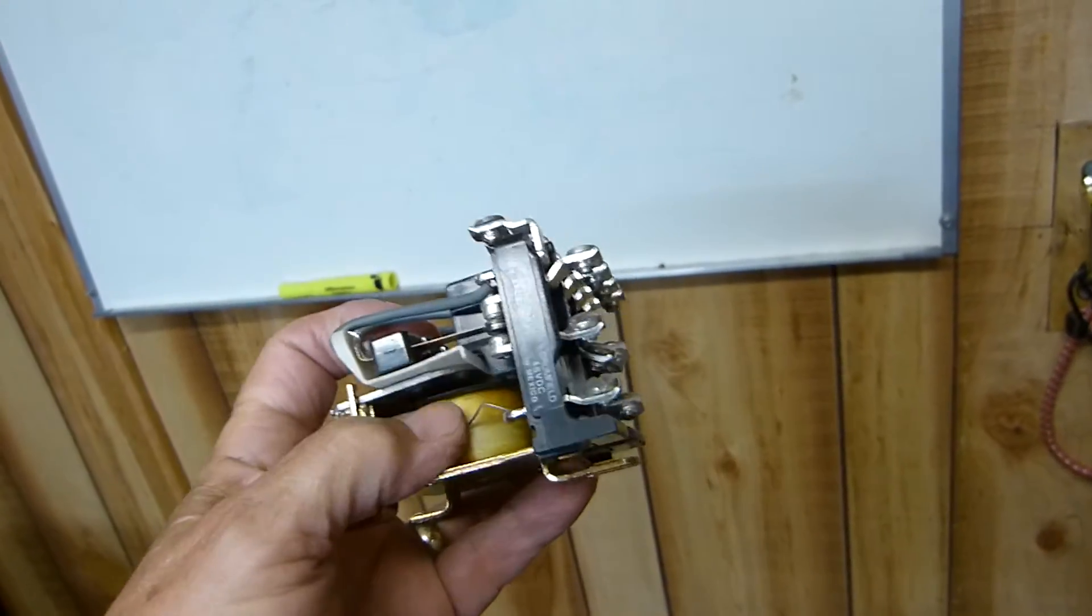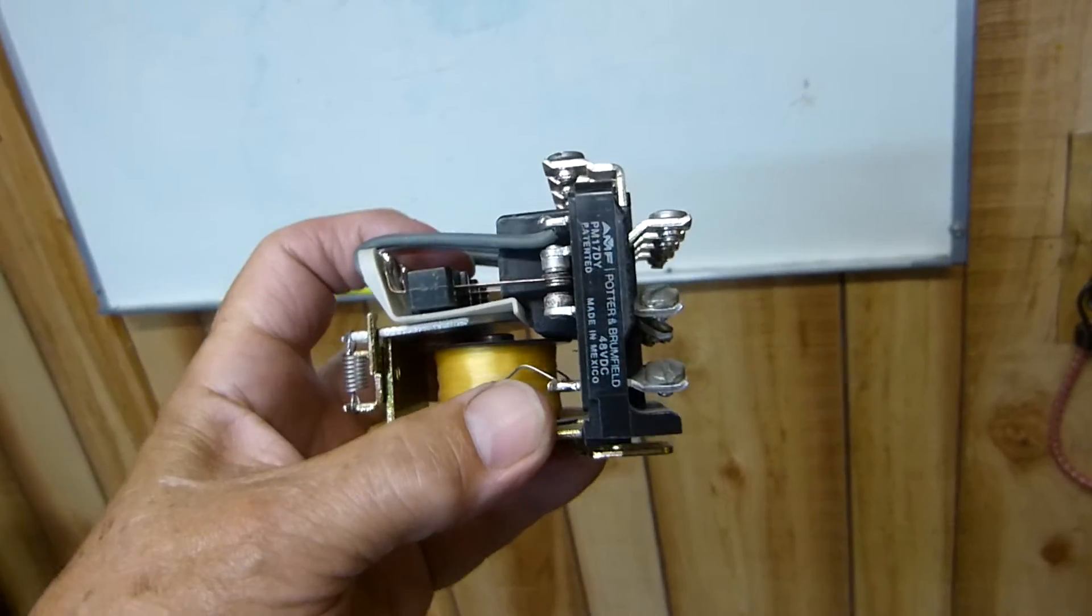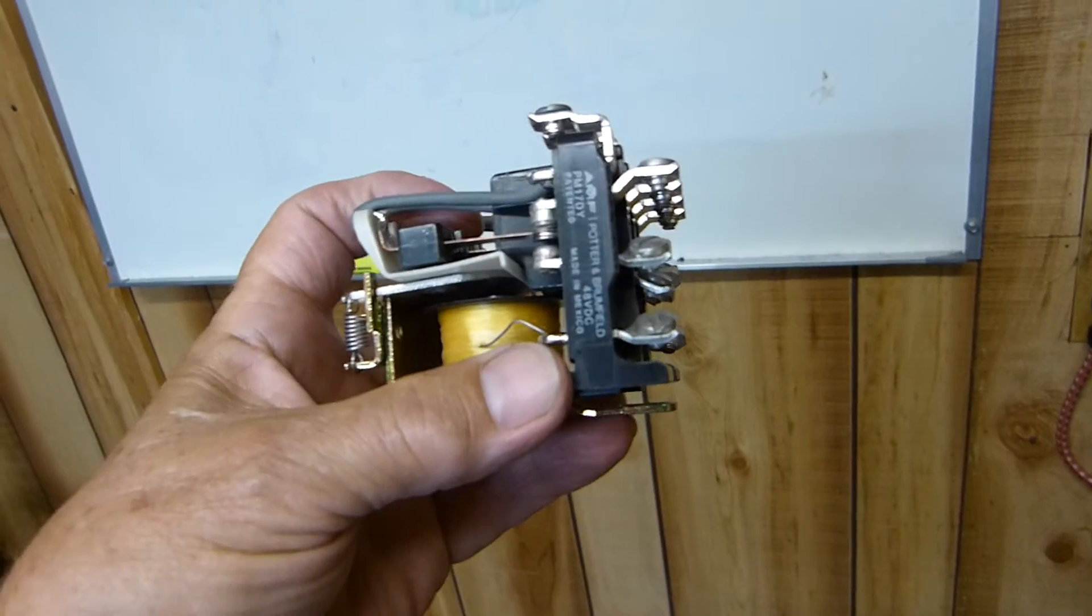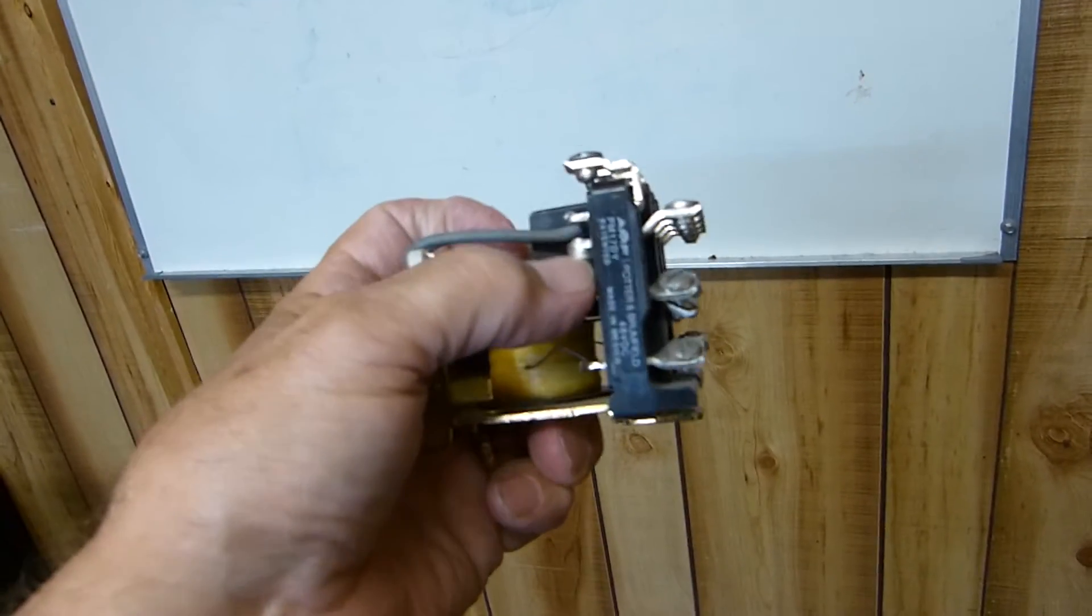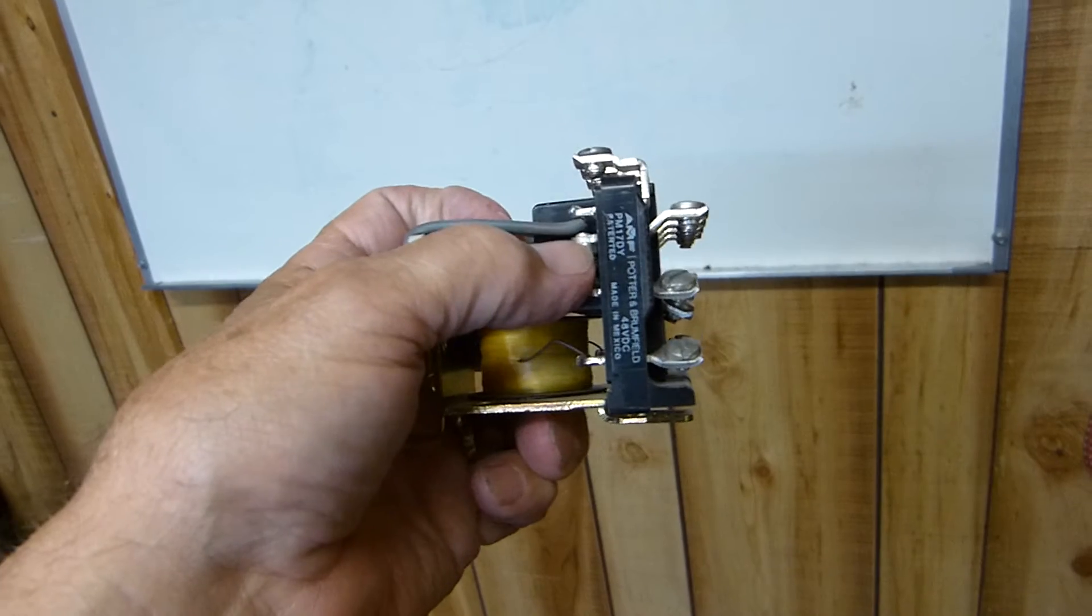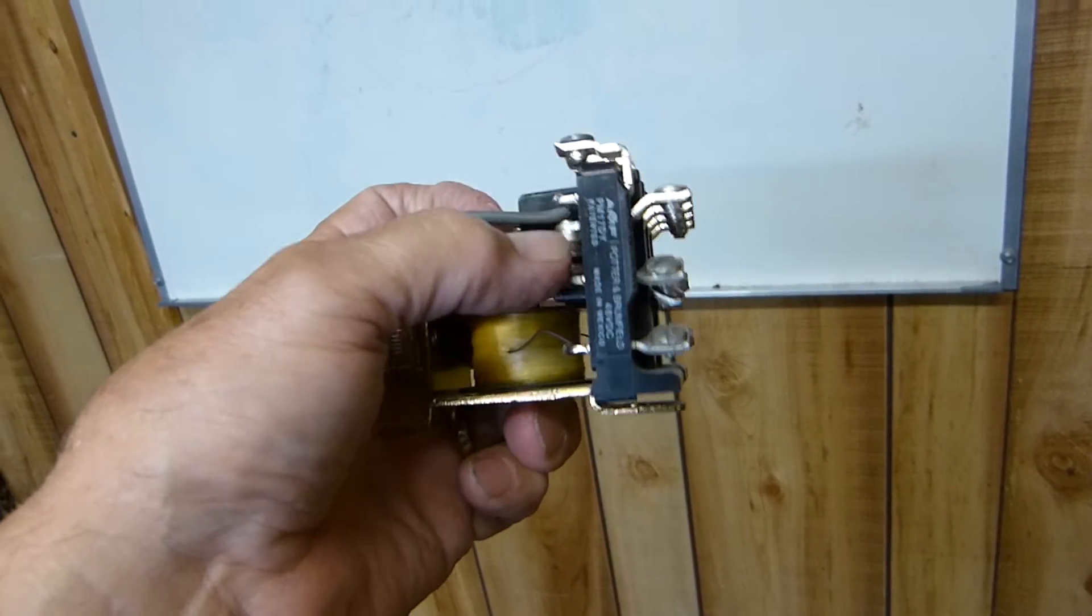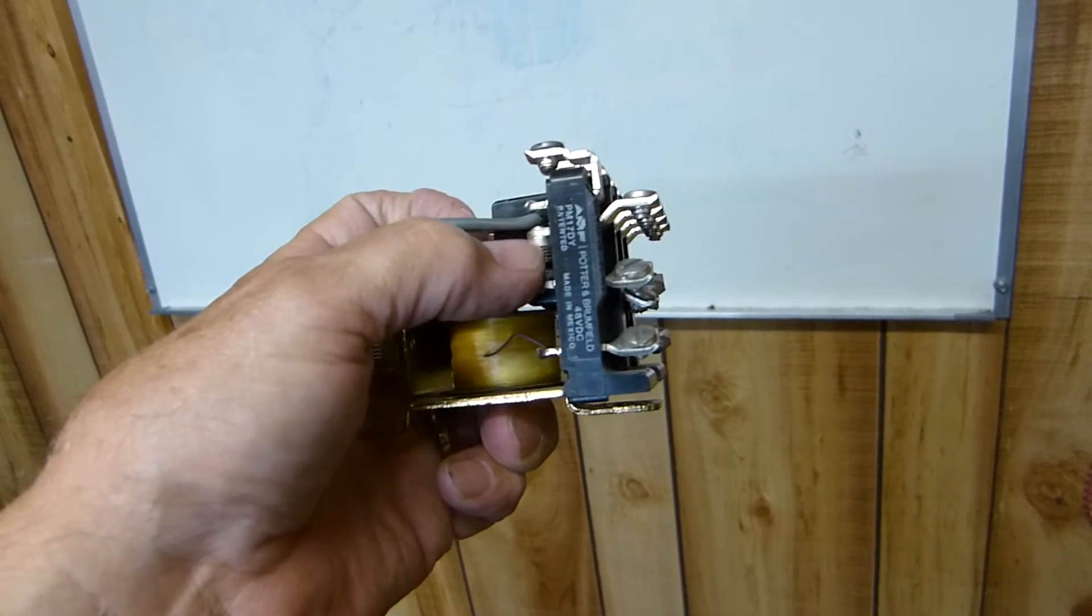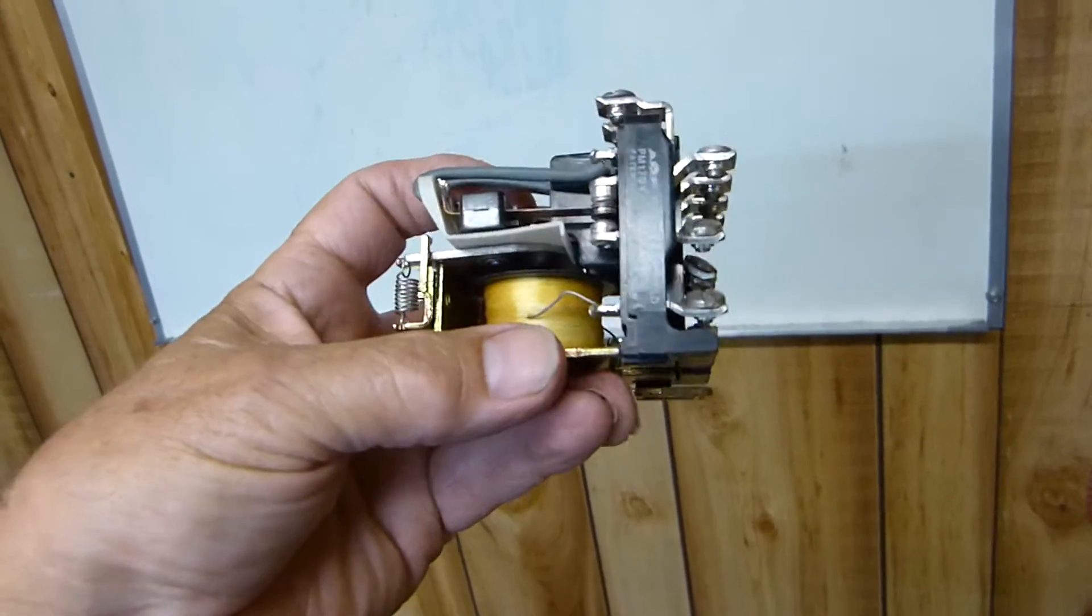First of all, here's a very simple relay. This is a 48 volt coil. I'll show you how they work. This right here, the moving part, is called the common. And this one up here where it's touching while it's just in its non-installed state, this is called the normally closed contact. This is called the normally open, NC and NO.